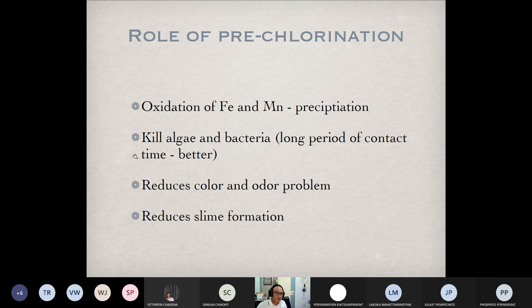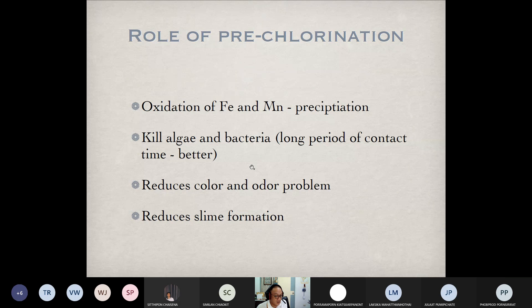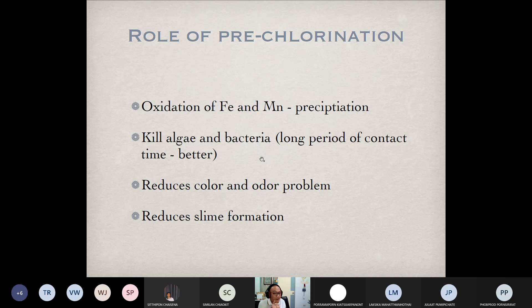These are the objectives of pre-chlorination. However, the major objective is not to kill germs or disinfect microorganisms. We just add a certain amount of chlorine to kill some algae and bacteria, but not to disinfect germs. So we don't add too much — just enough to fulfill these objectives. If there are no iron and manganese, no color and odor problems, pre-chlorination may not be required.